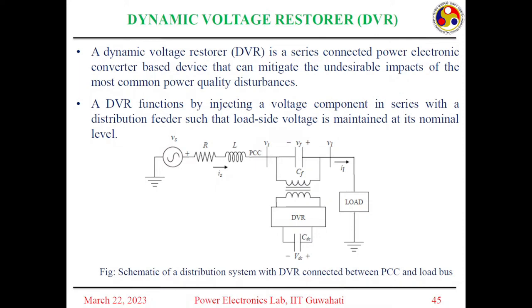Here also we only require a capacitor because DVR doesn't supply any active power to the system. We only require a capacitor for the DVR, we don't need any DC voltage source. Since we are injecting voltage in series with the feeder voltage, the DVR can be used to mitigate the effects of voltage sags, voltage swells, and voltage imbalance. So all problems related to the supply voltage can be mitigated using a DVR.